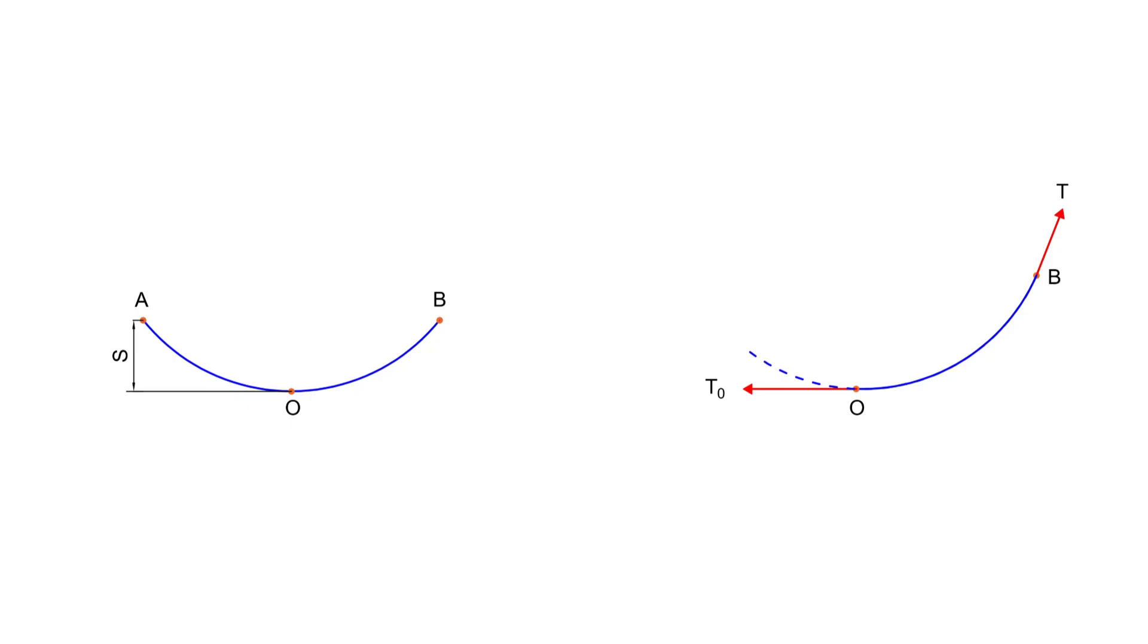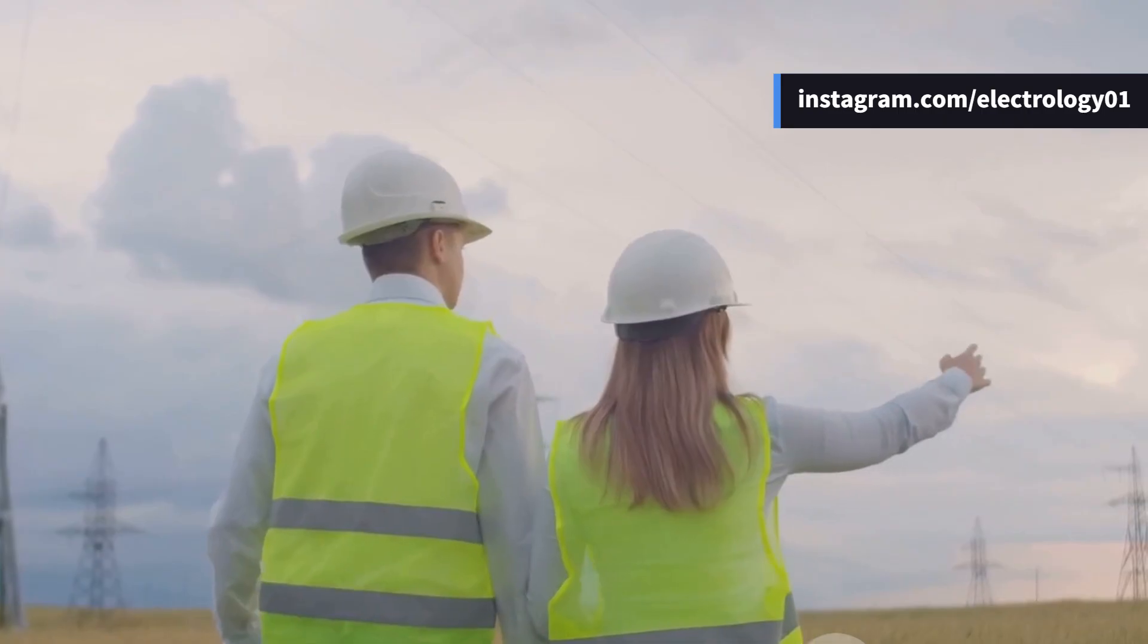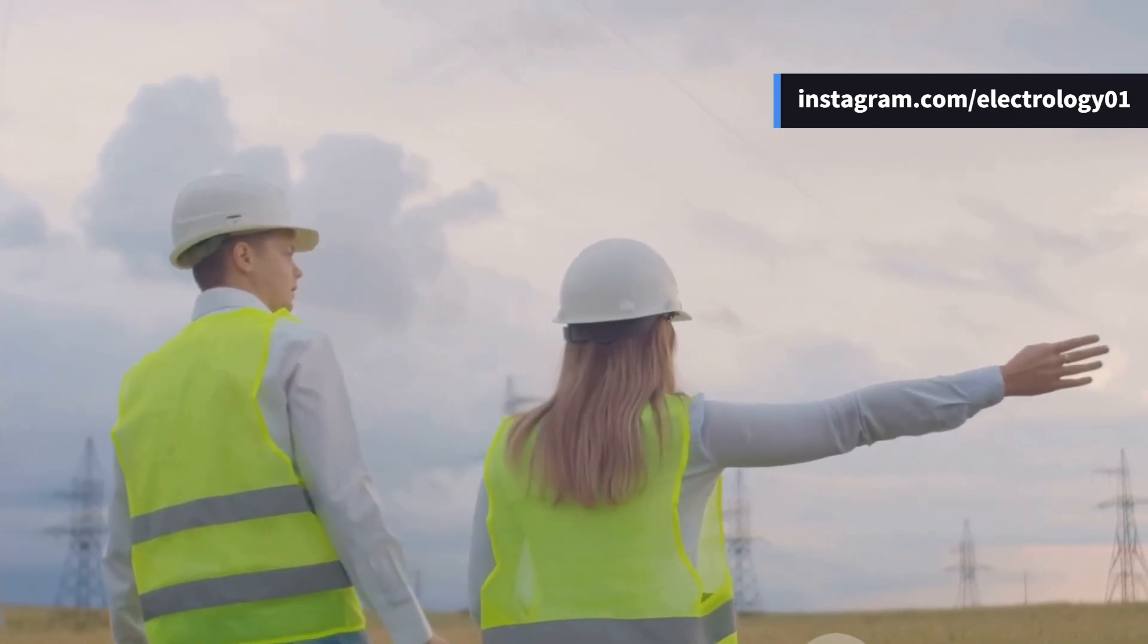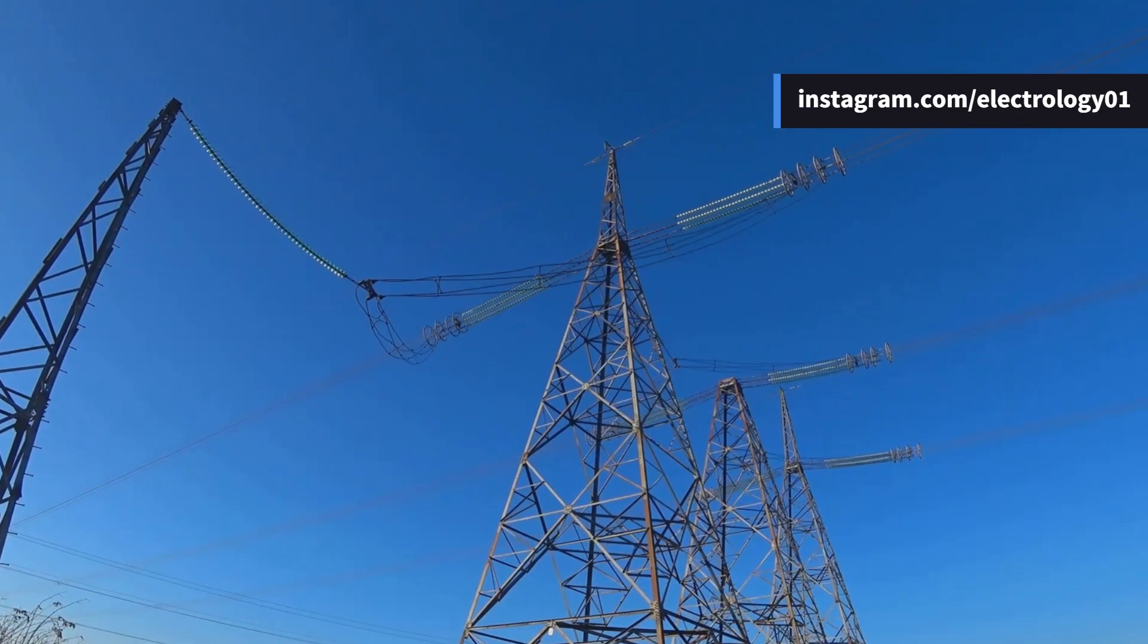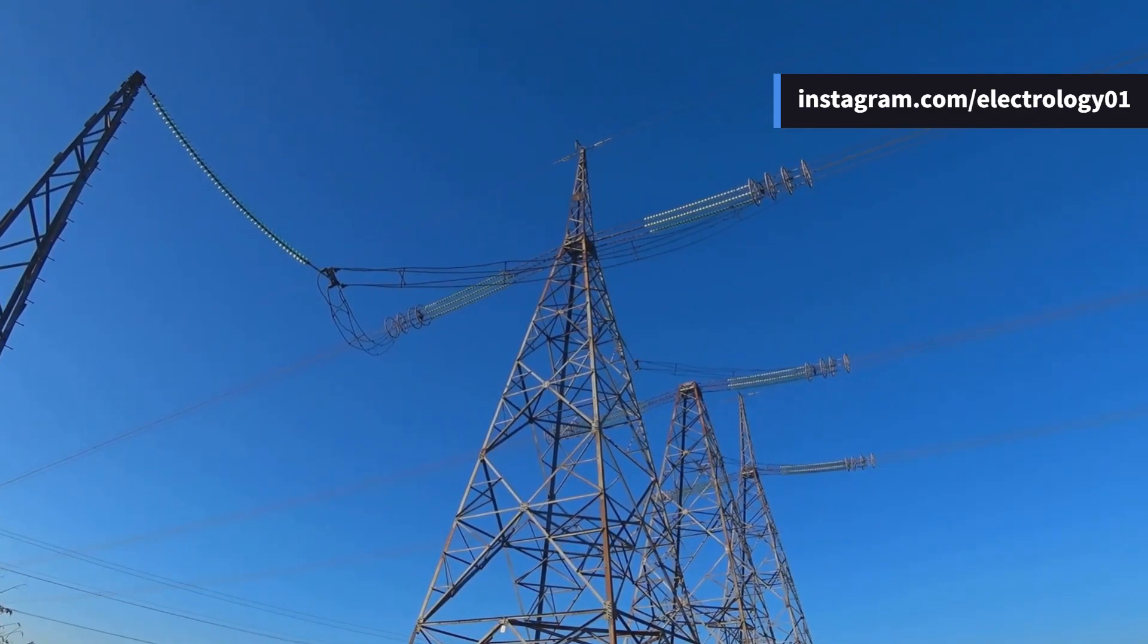Here's the catch: if sag is small, the wire is tight which means tension is high and there is a risk of snapping. If sag is large, the wire is loose, tension is low, but poles need to be very tall. So in practice, engineers make a compromise between minimum sag and safe tension. By the way, do you think sag should be more in longer spans or shorter spans? Drop your guess in the comments.